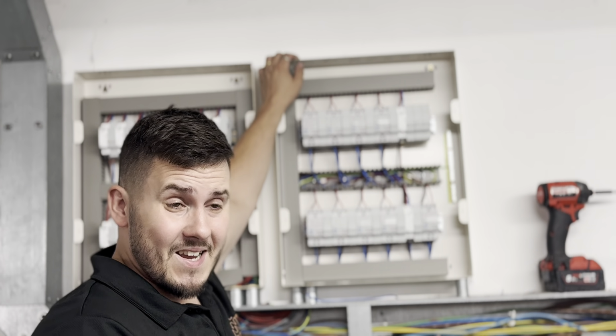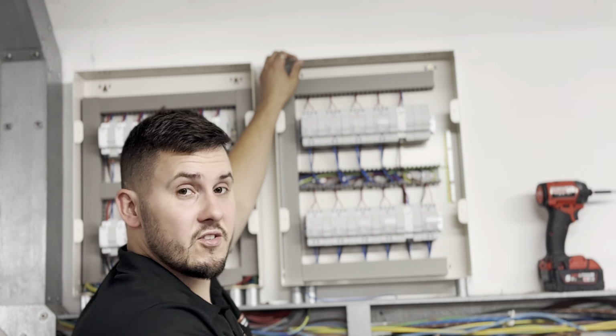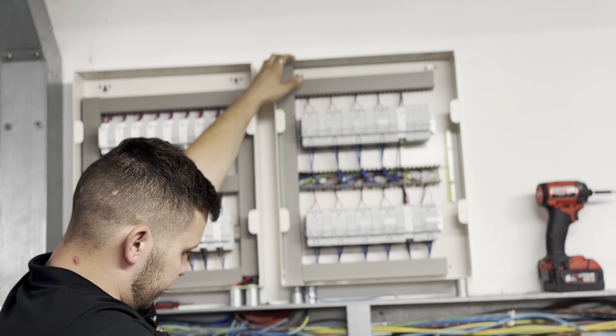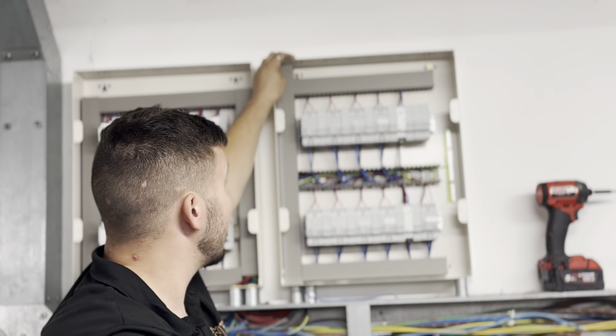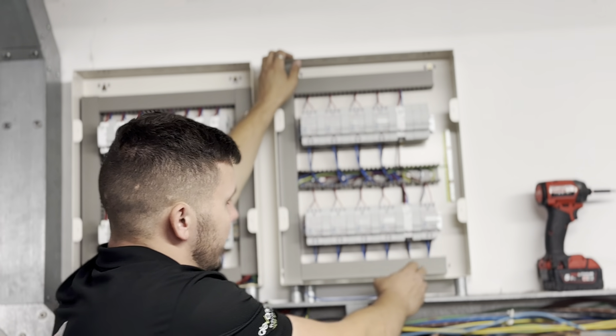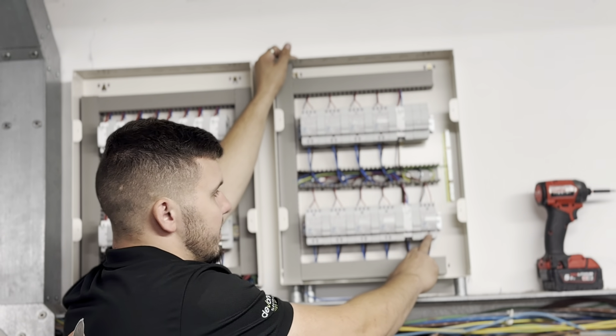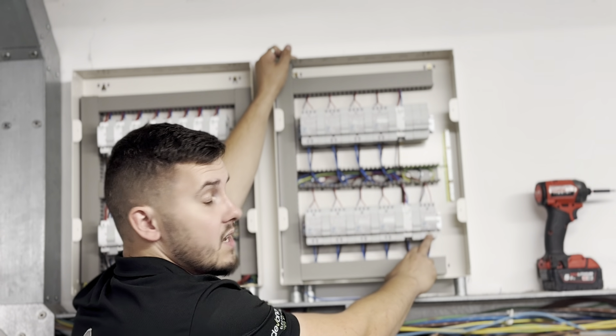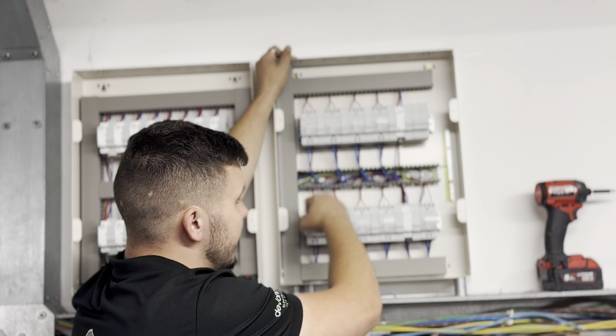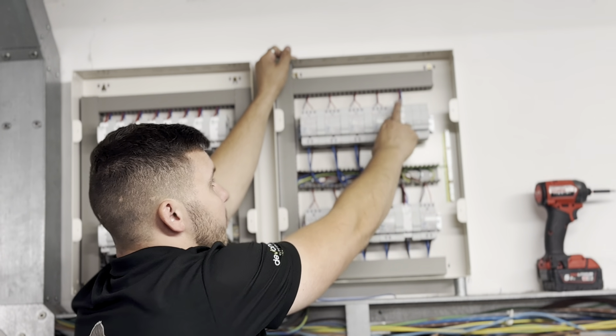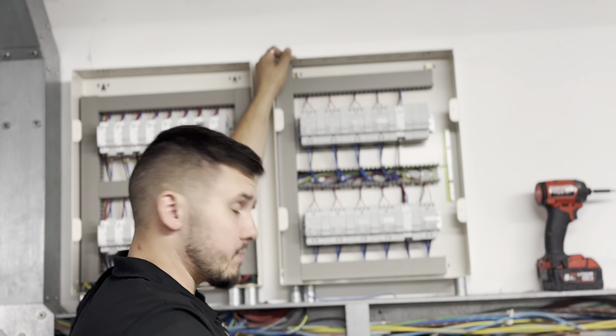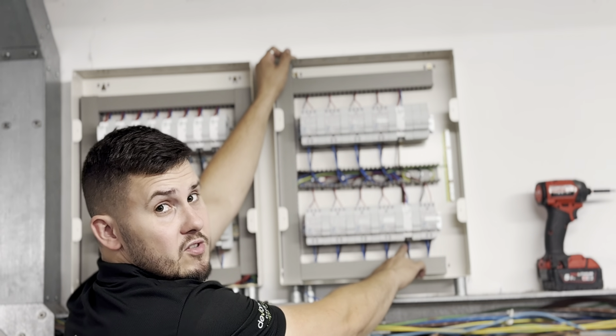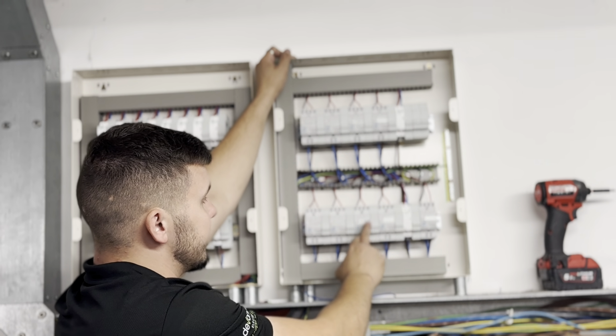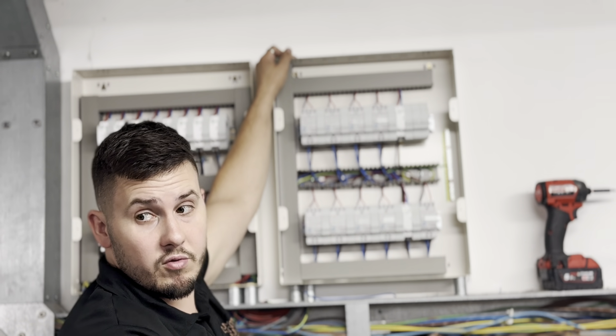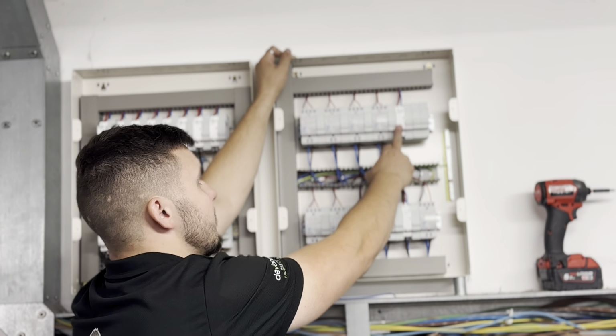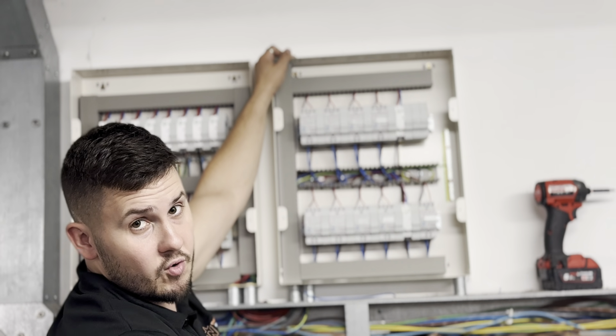So, what I was saying, this is our main transformer. We have a permanent feed just looping off one of our lighting supplies. It's coming up through and feeding this transformer on the primary side, then looping across into the incoming side of both our contactors. The outgoing side of those contactors feeds the primary side of all 4 of those transformers for one, and this contactor feeds the primary side of those 4 transformers.